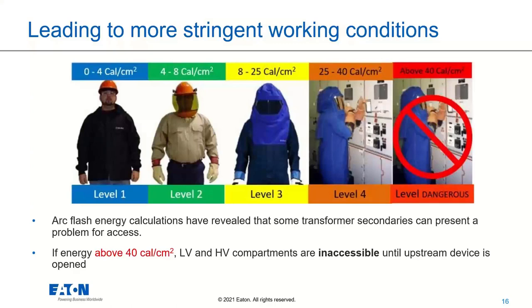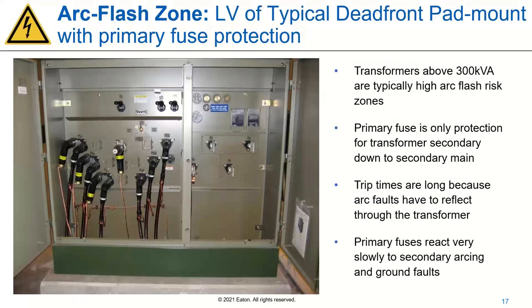Or what arc flash levels I have, I can use something that's going to factor in 1584's updated requirements. It's going to factor in those enclosure sizes and the electrode configurations. And it's going to give you a more concrete answer on what you're dealing with, regardless of whether you're talking integrated equipment that we're featuring here or just more of a traditional lineup, no matter what you do. So just to highlight some of those standard features and standard zones, if you're looking at a normal pad mount transformer, you've got things that are inside of the arc flash hazard zone. You've got nameplates, you've got gauges, you've got drain valves, in some cases bayonet fuses on the primary, load break switches, sectionalizing switches.